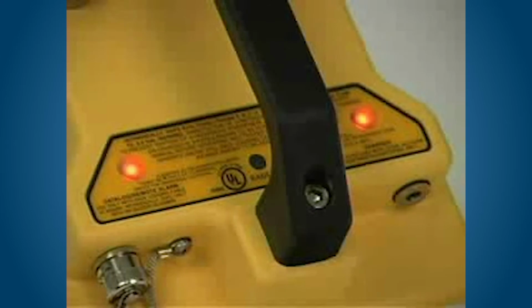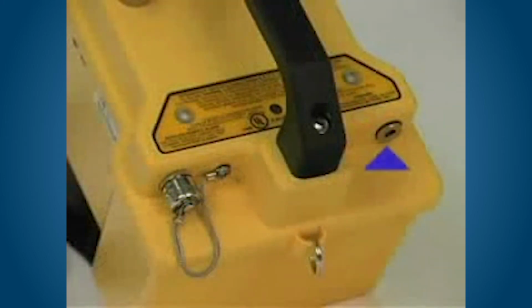2 bright red LEDs provide a visual alarm for gas concentrations and malfunctions. They are both located on the top rear of the Eagle's case for optimum visibility. The battery charger connector is mounted on the top right rear of the instrument. An external RKI battery charger can be connected here to recharge the NiCad type batteries, which should operate the instrument for up to 18 hours between charges.